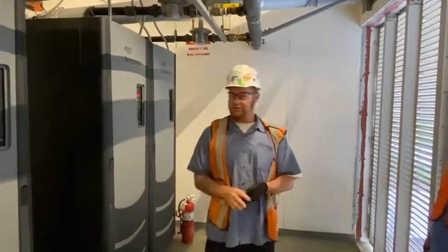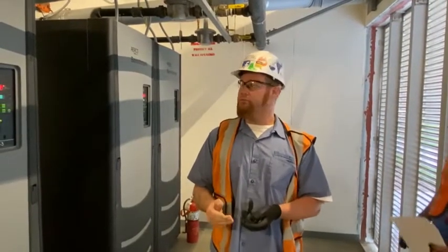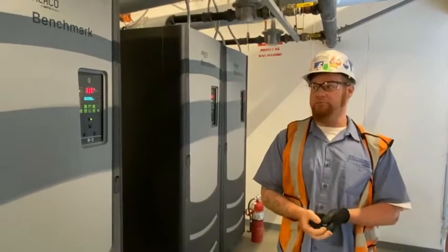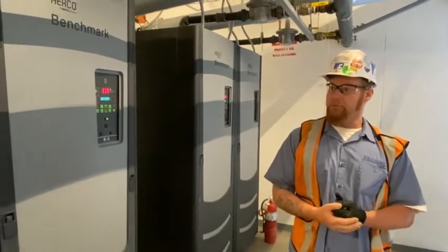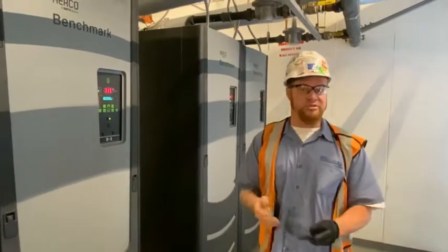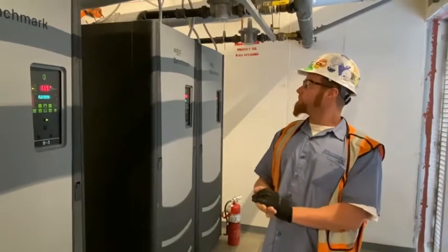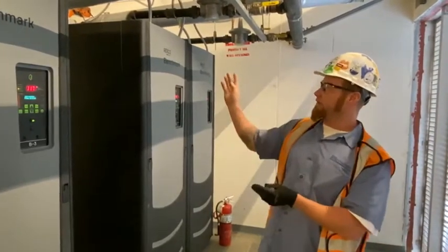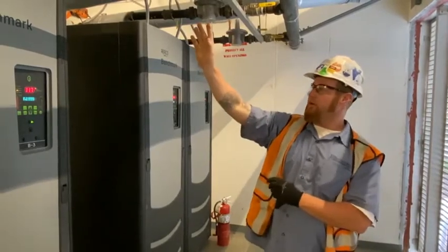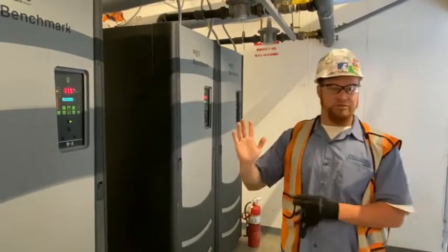I'm Shawn with Air Treatment Corporation, here for AERCO. We have four Benchmark 2000s, which are low-NOx condensing boilers. They are currently set up in a BST configuration — Boiler Sequencing Technology. They have isolation valves on each inlet piping, so we are staging them to meet our demand.